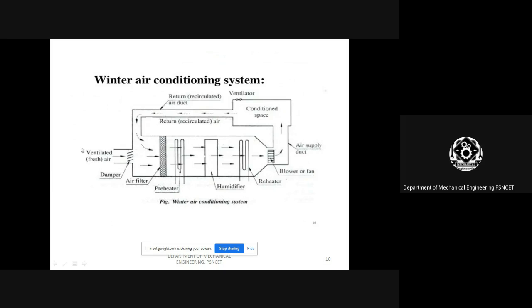From outside, atmospheric air enters through this damper. This damper changes the direction of the air towards upward or downward, and there is a filter for the big impurities. Here there is a filter with very minute filtration. Air with minute filtration is obtained, and then it is passed on to the preheater. Because in the winter season, the surrounding temperature is very low. So for the human comfort condition, the heat is gradually increased. For that purpose, we have a preheater.